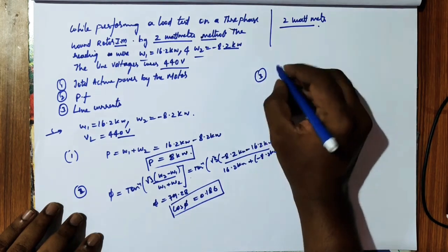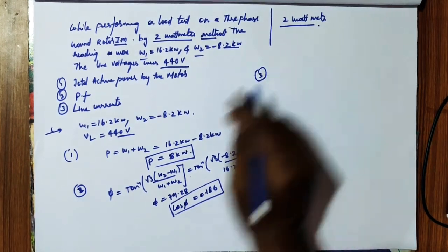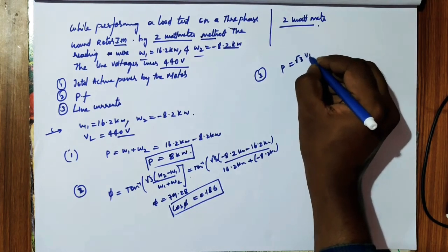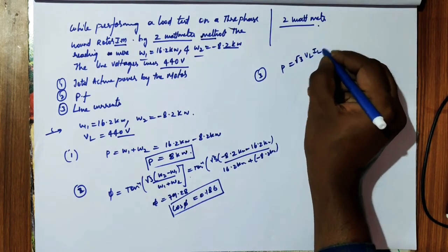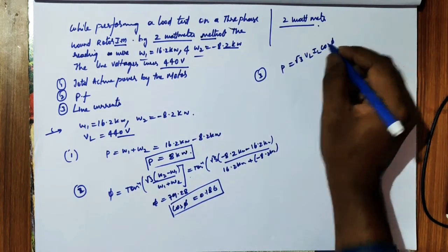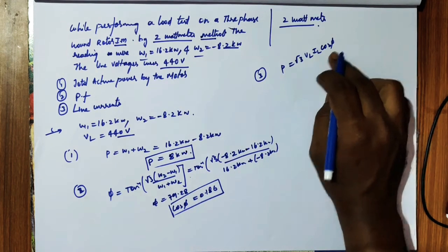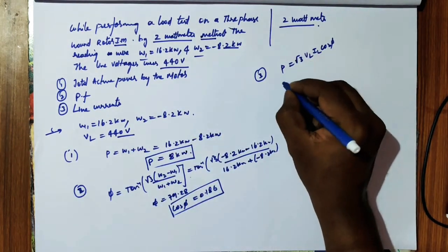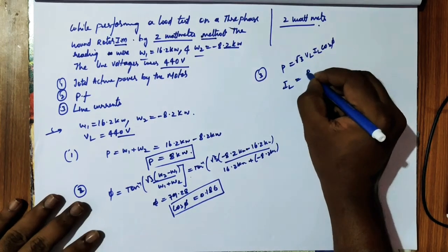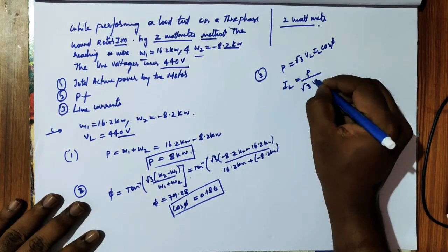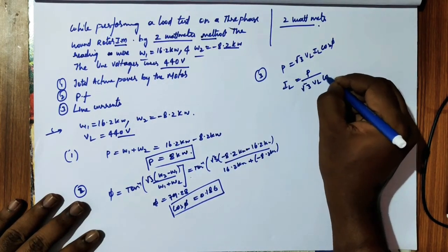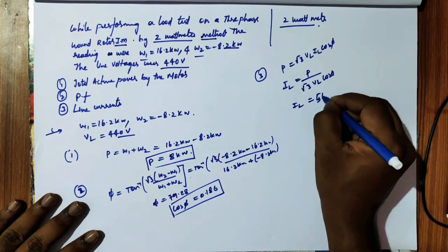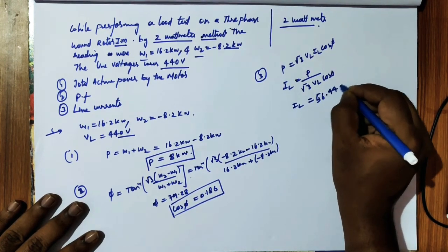The question also asks for the line current. Using the formula P = √3 × VL × IL × cos(phi), we can find the line current: IL = P divided by (√3 × VL × cos(phi)). Substituting the known values gives IL = 56.44 amps.